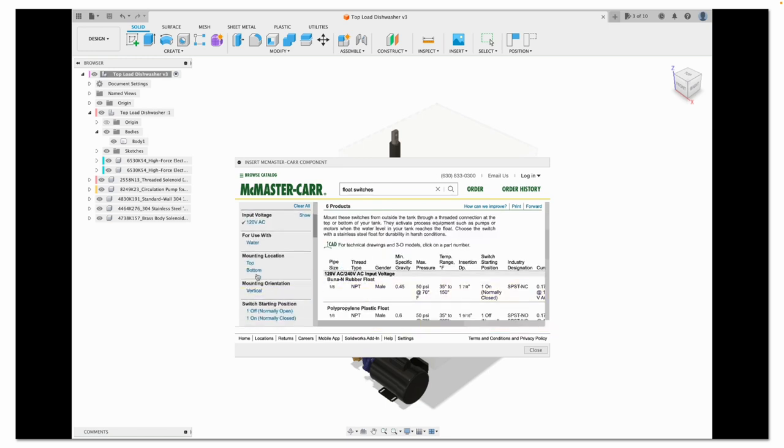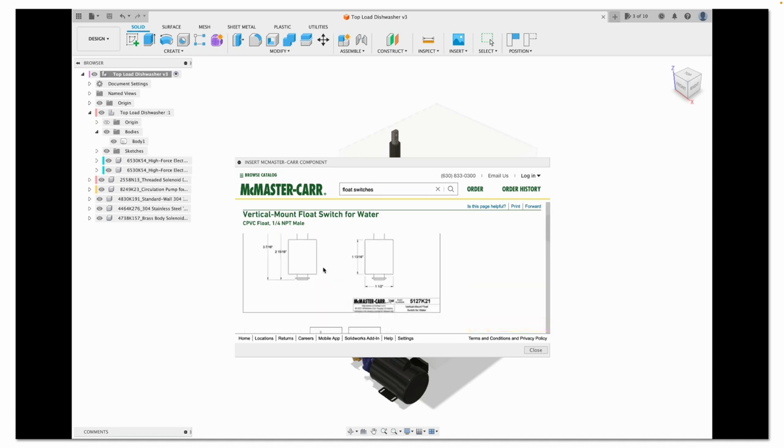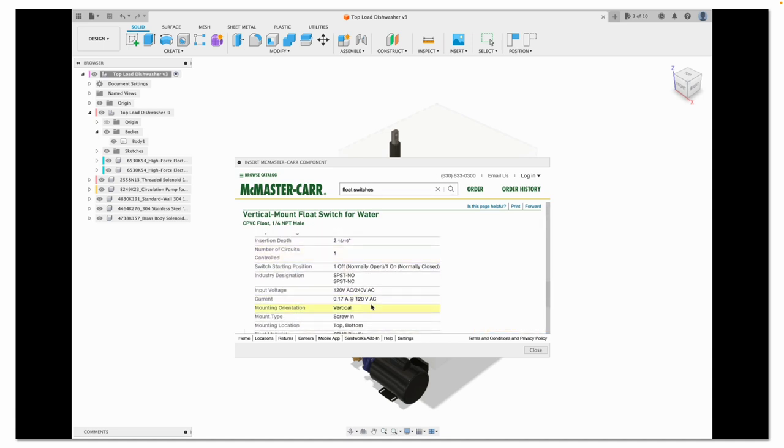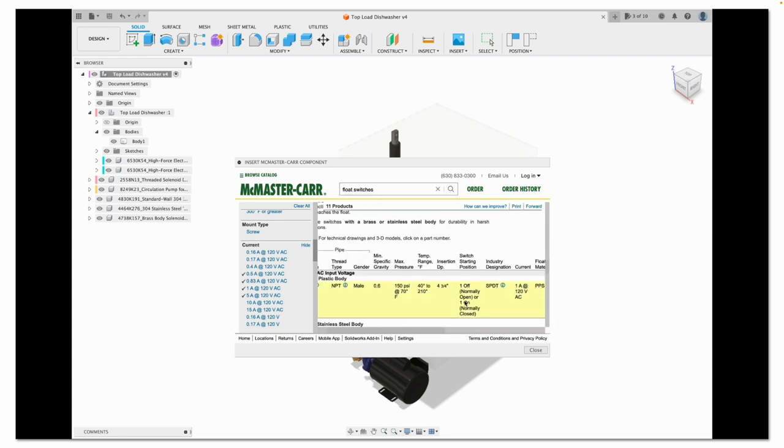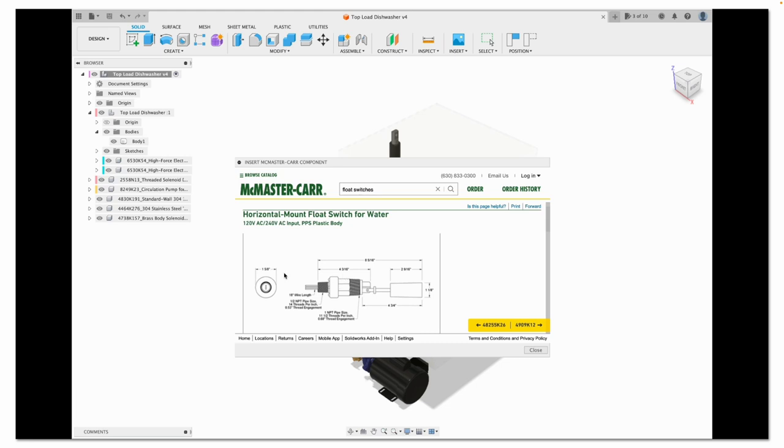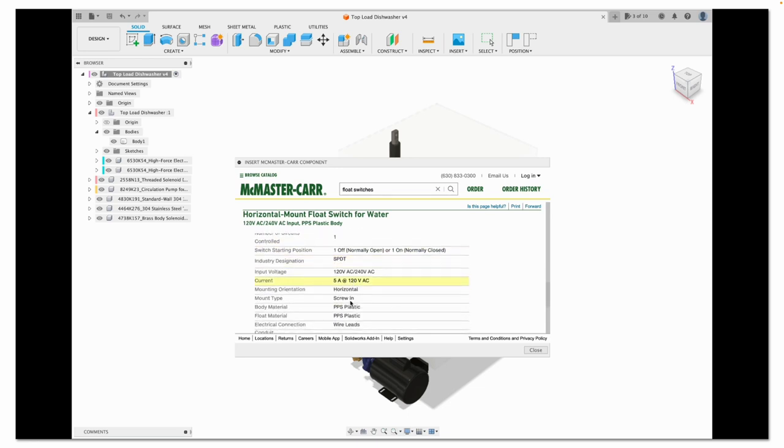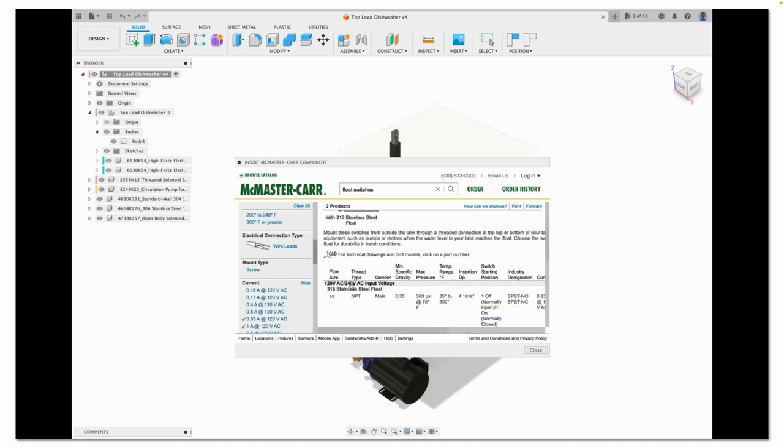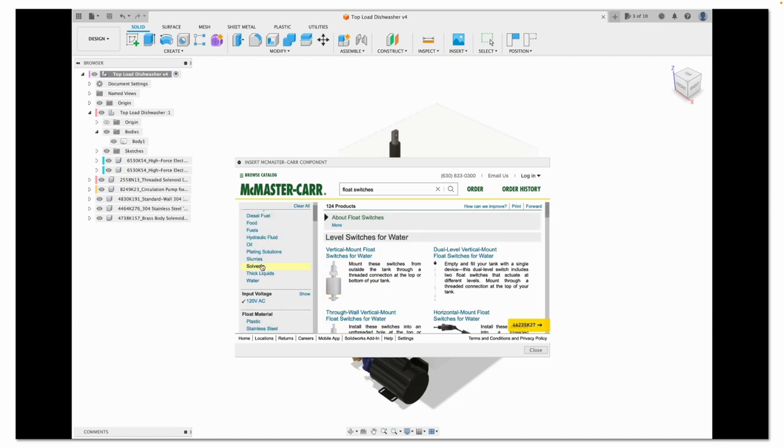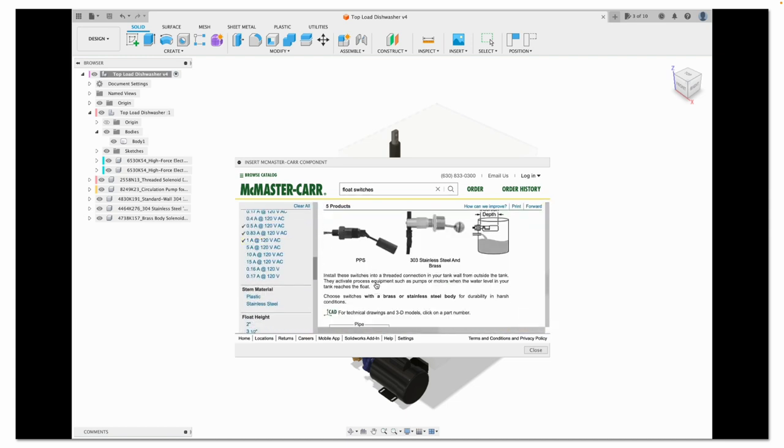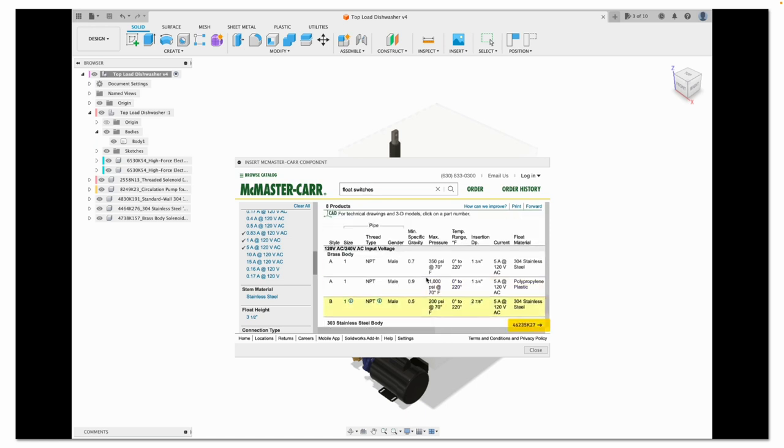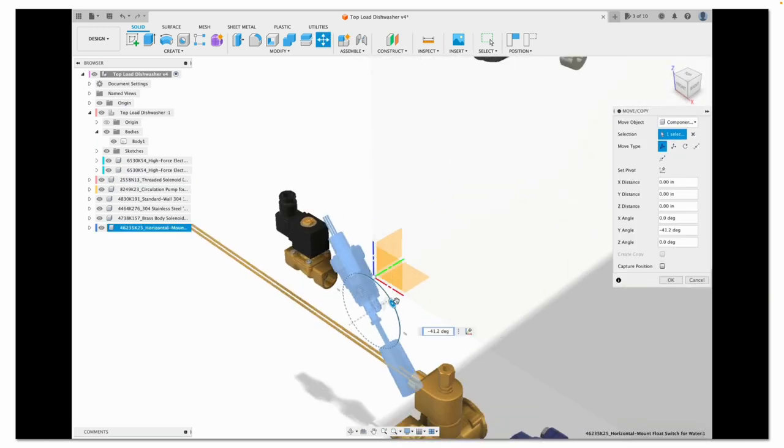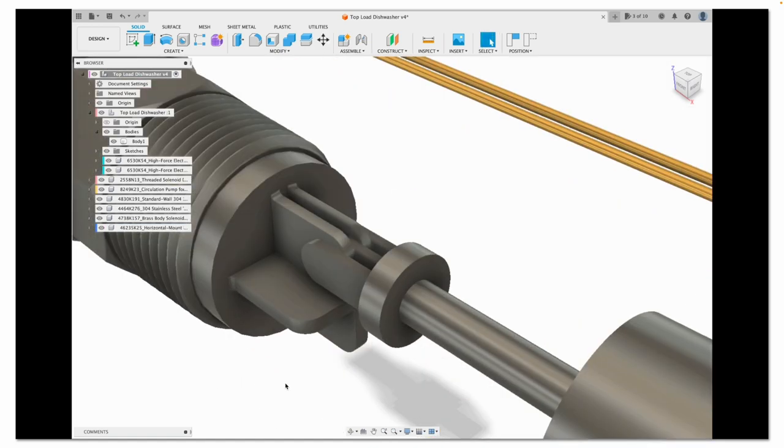Now I'm adding a float switch. The float switch protects the pump, so we don't run our pump dry and let it cavitate. When the float switch floats up, means there's enough water in there to run the pump. When it floats down, it tells the pump to shut off. And there's vertical mount, horizontal mount, made out of different materials, plastic float switches, stainless steel. Depending on your application. And again, these are commonly available. Grainger, McMaster Carr, SupplyHouse.com, look on Google, eBay, Amazon, etc. So again, common parts.